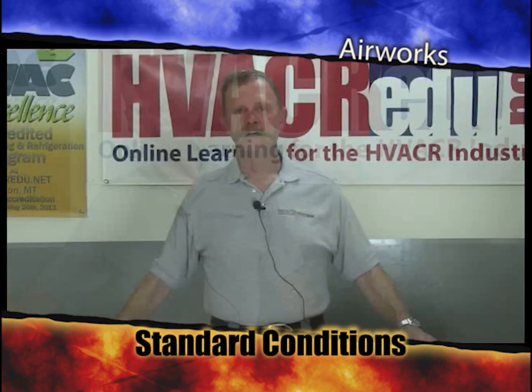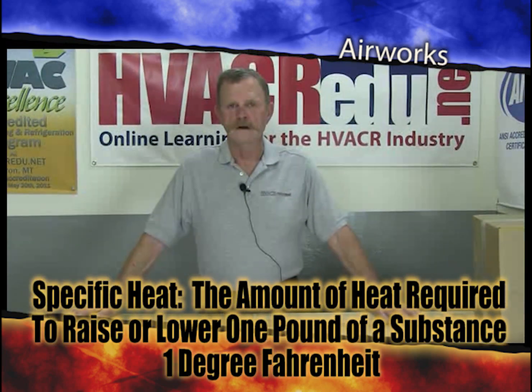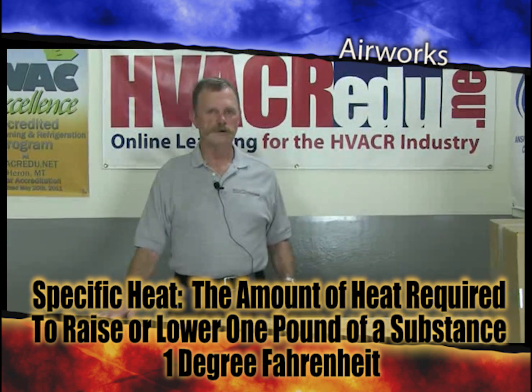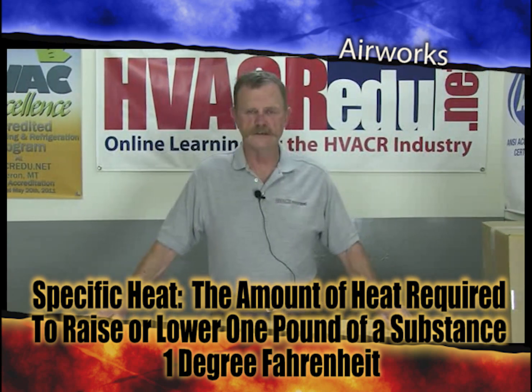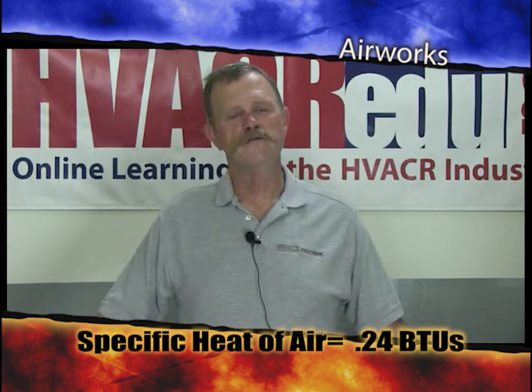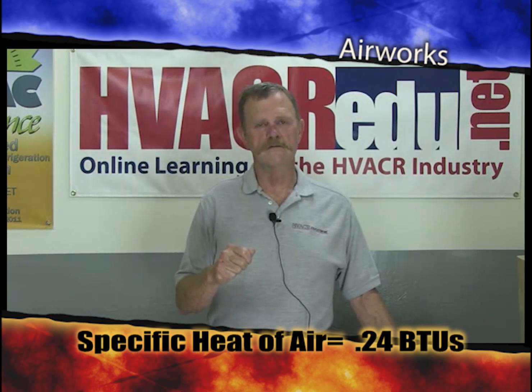The next thing that's specific about standard air is specific heat. And if you recall, specific heat is the amount of heat required to raise or lower 1 pound of a substance 1 degree Fahrenheit. The specific heat of air is 0.24 BTUs. So just a shade under 1/4 of a BTU, if you add 1/4 of a BTU to a pound of air, you will have an increase of 1 degree Fahrenheit. If you take away 0.24 BTUs from a pound of air, you will have a drop of 1 degree Fahrenheit.